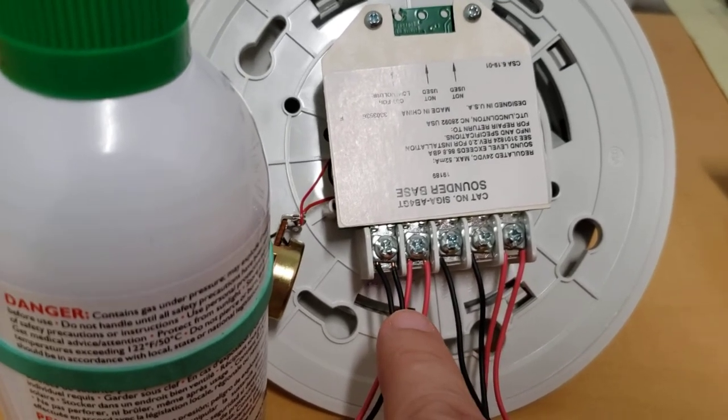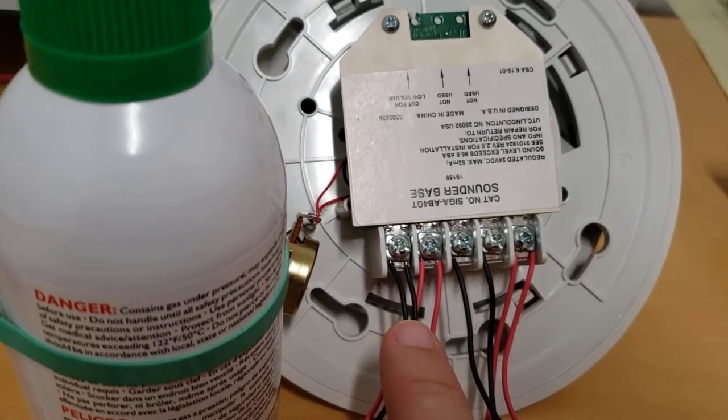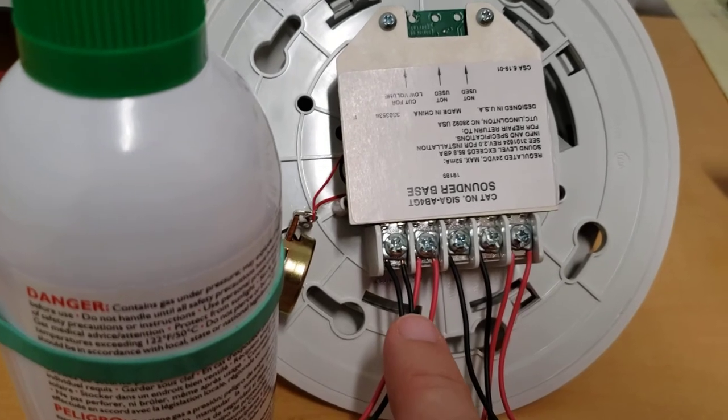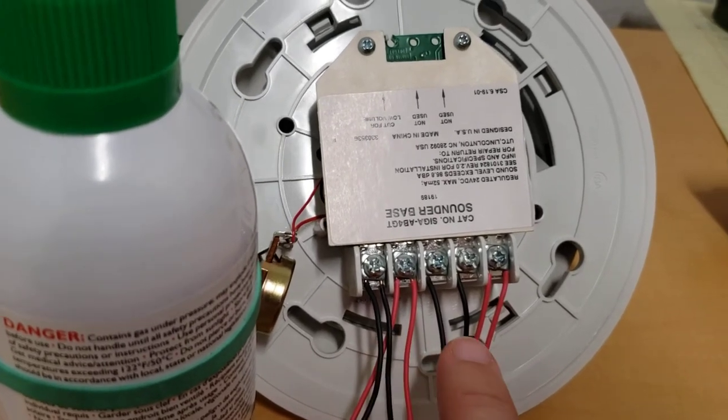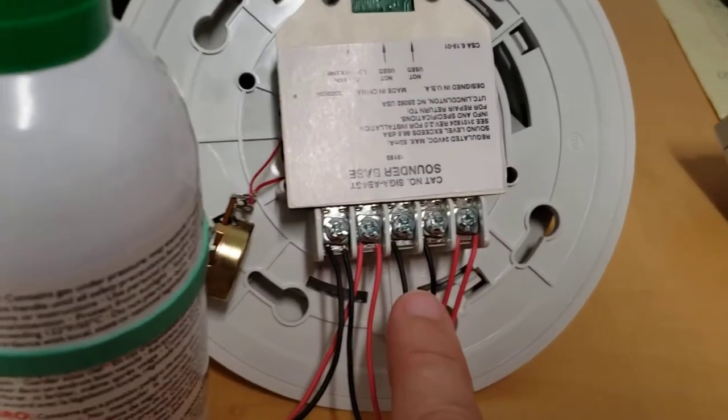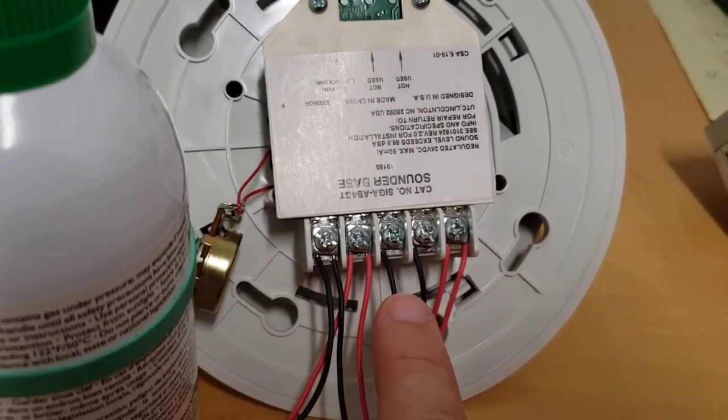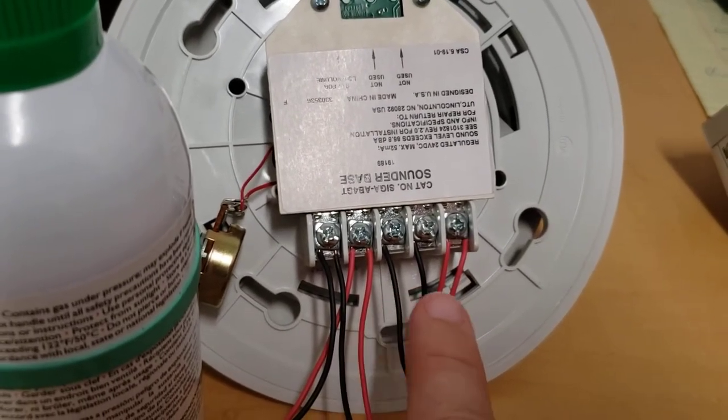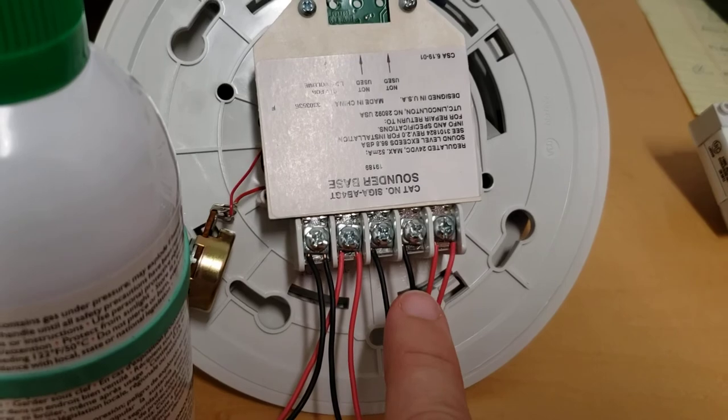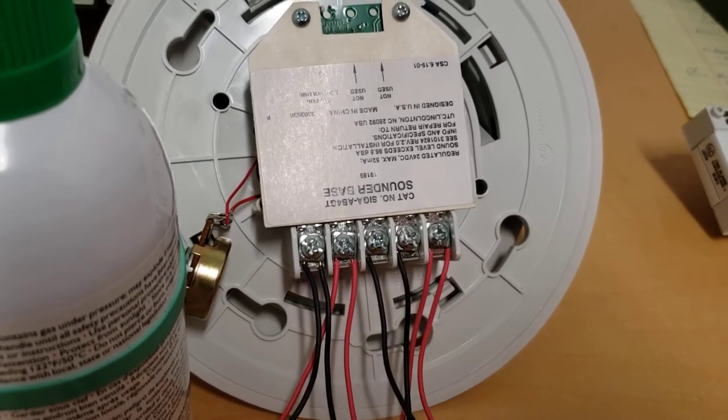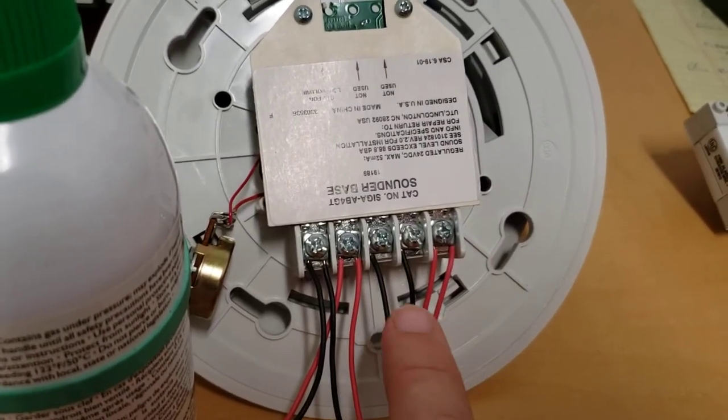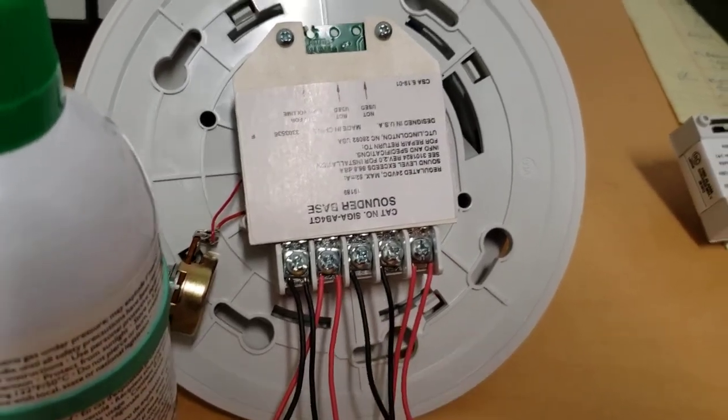The terminals are labeled for their active state not their normal state. The Signature Series SLC wires as you would expect with positive being common and negative in and negative out being their respective colors of black and red as you see there as normal.